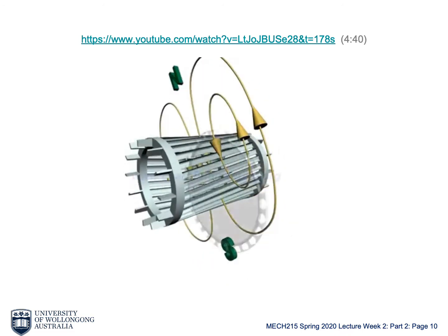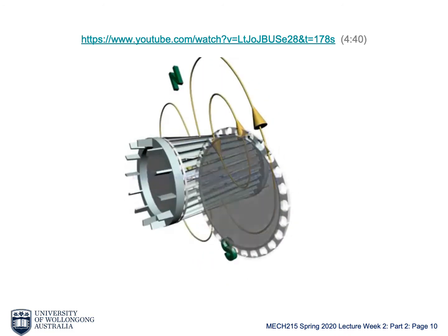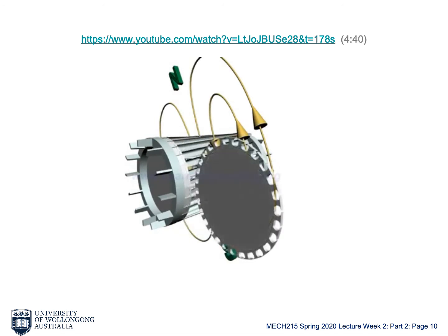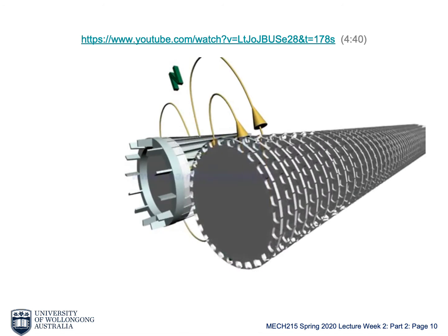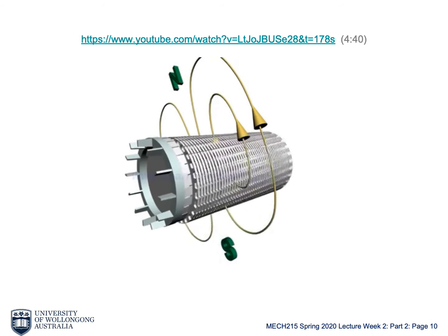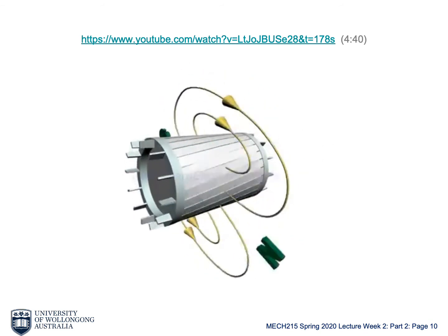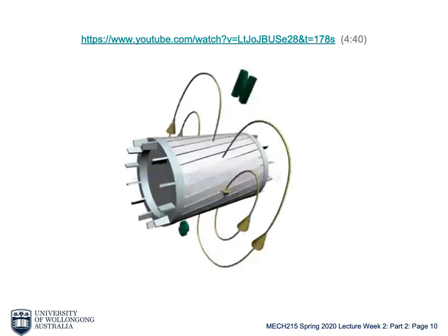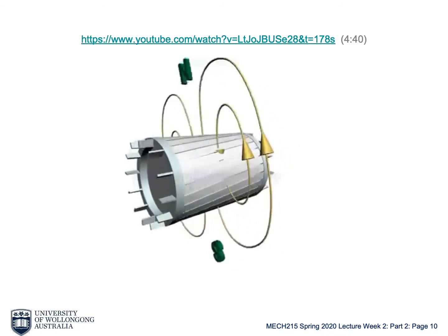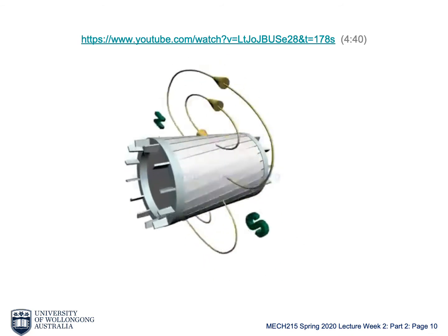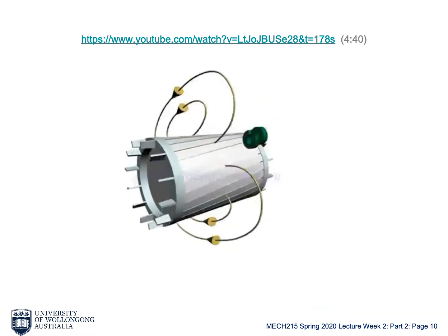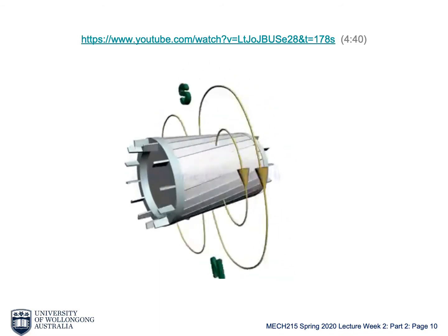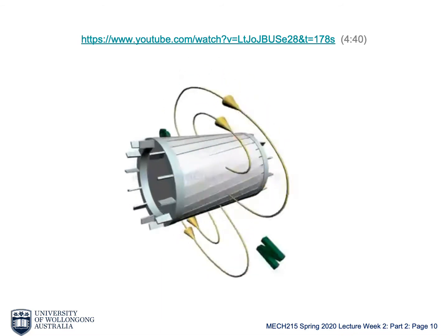To aid such electromagnetic induction, insulated iron core laminations are packed inside the rotor. Such small slices of iron make sure that eddy current losses are minimum. This is another big advantage of a three-phase induction motor. It is inherently self-starting. So, you can see here that both magnetic field and rotor are rotating. But at what speed will the rotor rotate? To obtain this answer, let's consider different cases.